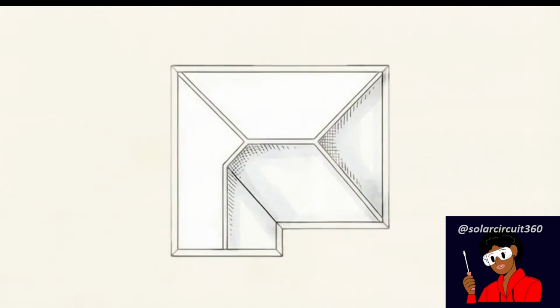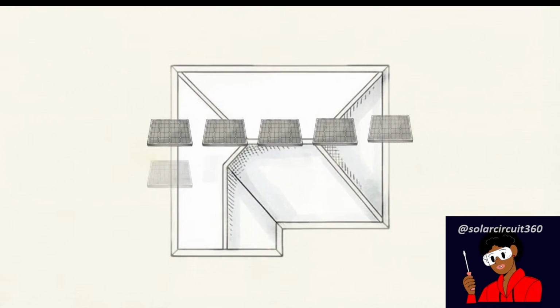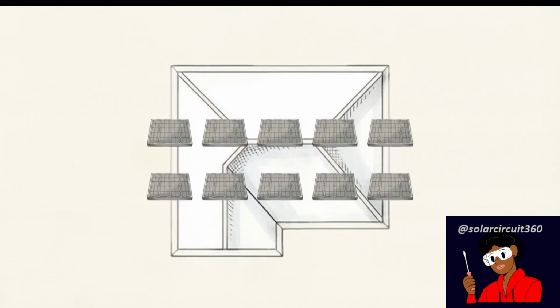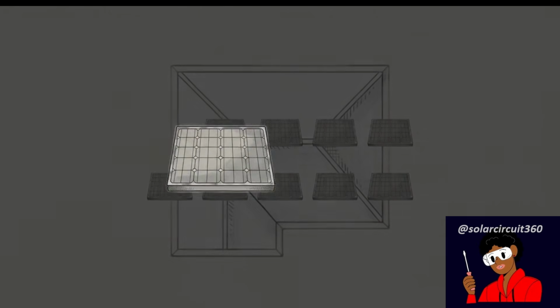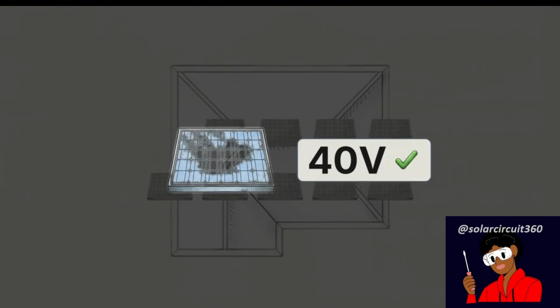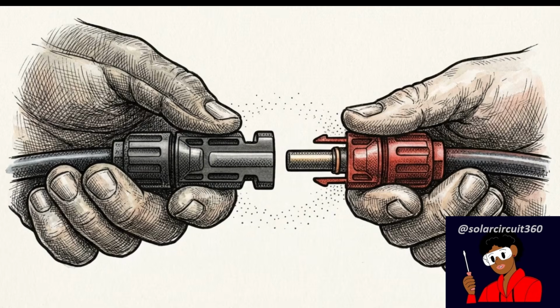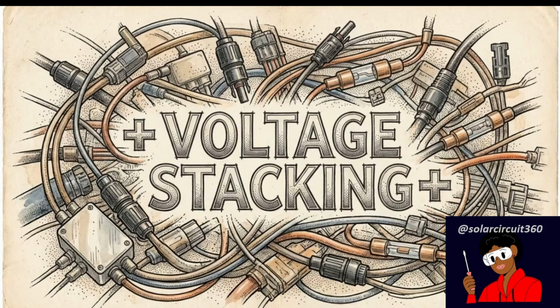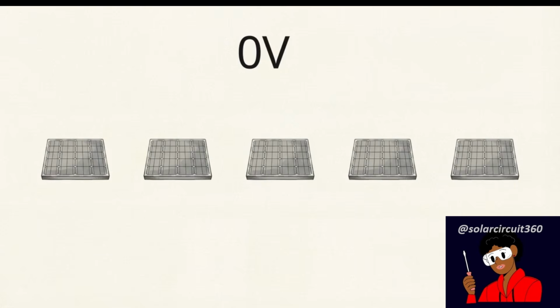To understand how an arc starts, we must look at the modular nature of solar installations. These systems are constructed by linking individual panels that operate at relatively low, safe voltages. However, when you wire these panels in a series, you trigger a mechanical reality called voltage stacking. The baseline voltage of every single panel adds up together, multiplying invisibly as the string gets longer. This animated diagram demonstrates the math in action. We have 5 standard 40-volt panels wired in series.